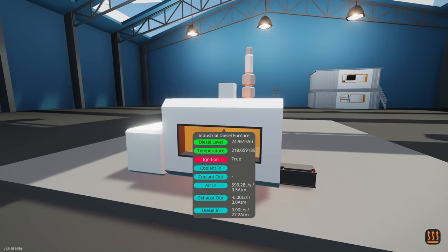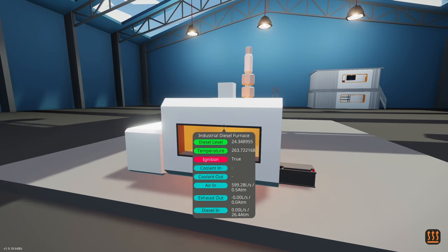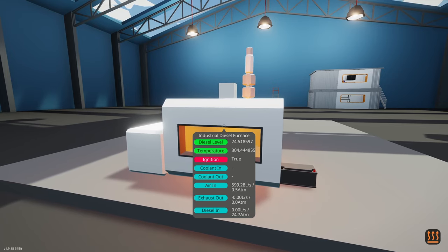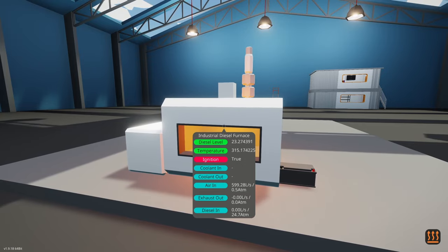Any heat we do not need comes from fuel we are burning that we didn't need to burn. So if our temperature is super high and we don't need it that high, we're burning a lot of diesel. If we can throttle our air intake, we can reduce our temperature and burn less diesel. We also don't waste as much heat into the room. We're up to 303 degrees.